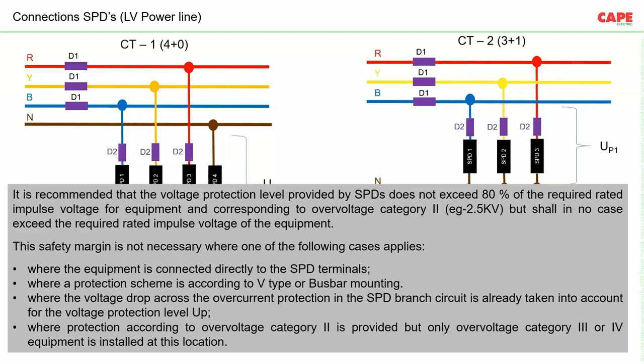This safety margin is not required where the equipment is directly connected to the SPD terminals — reducing wire length significantly and minimizing voltage drop — or where a protection scheme using V-type or bus-bar mounting is applied. Bus-bar mounted SPDs are available in the market; due to their shorter connecting lead lengths, voltage drop is very low and optimum protection can be achieved.